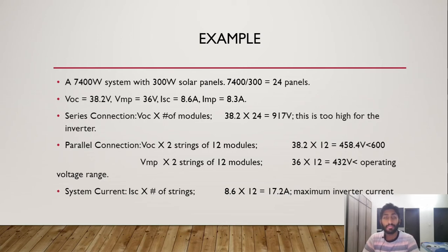Now you want to calculate system current. System current is to multiply the number of strings that we have, because in parallel the current adds up. Number of strings we have is two, multiply that with the maximum current Isc, so Isc is 8.6 amps times 2 gives us 17.2 amps, and you compare that with the maximum inverter current at DC. The maximum inverter current at DC specifications is, for example, 20 amps - 17.2 amps is less than that, so that also works and meets.